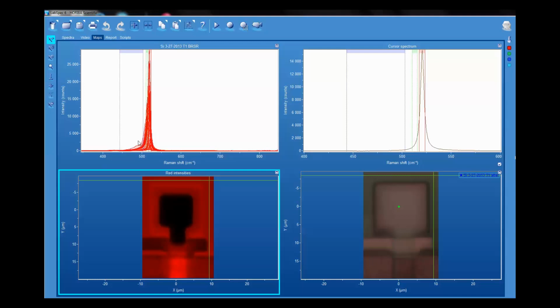Again, the excitation wavelength for our generation of the Raman image and all the hyperspectral data set that we have here is 532 nanometer excitation with 500 millisecond integration time. So each spectrum that you see when I move the cursor will be a result of half a second integration, and the image that we generated here is a result of moving the stage relative to the optical axis in 200 nanometer increments.